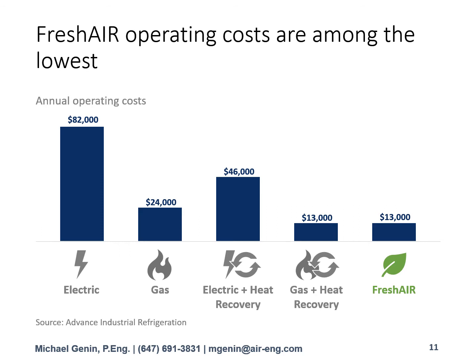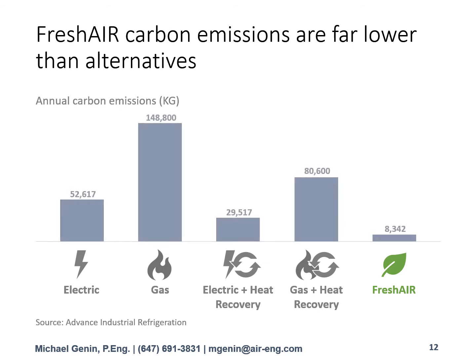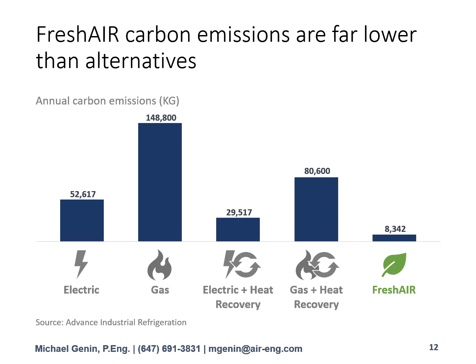And then we have fresh air active heat recovery, which is about on par with an efficient gas heat source and efficient passive heat recovery device. Where active heat recovery really thrives is on greenhouse gas emission reductions. So we've done the same simulation for greenhouse gas emissions, and as you can see from this graph, electricity, although more costly, has a sizable reduction in greenhouse gas emissions compared to burning natural gas. But by far the best is active heat recovery, and that's because it gets that seasonal efficiency of about 7-to-1.